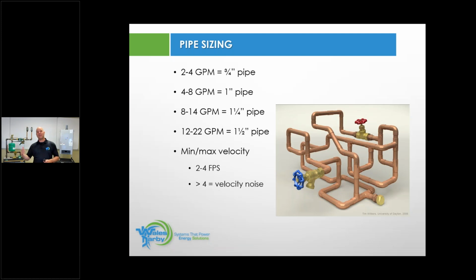But we need to have a minimum of 2 feet per second, because if I have a pipe going uphill and I have these tiny little pain-in-the-neck air bubbles in there, if I'm not moving that water at least 2 feet per second, I don't have the ability to move those air bubbles within the system. Let's say I'm at 1 foot per second, those air bubbles will stay attached to the pipe, and then they're eventually going to work their way up to the second floor, and they're going to have an air party, which means you have a service call to go bleed that circuit.